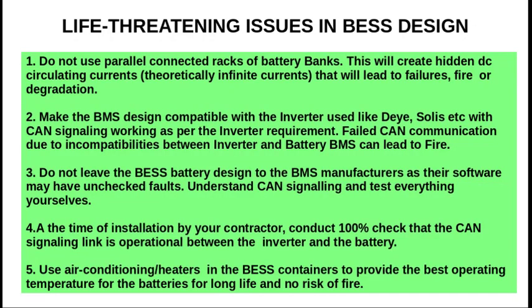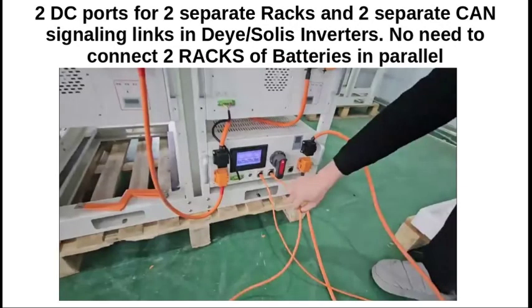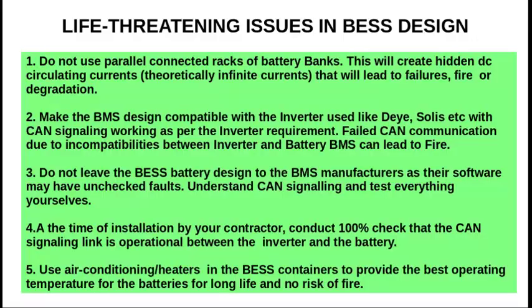Life-threatening issues in BESS design. 1. Do not use parallel connected racks of battery banks. This will create hidden DC circulating currents that will lead to either fire or failures or degradation of the batteries. Point number 2, make the BMS design compatible with the inverter used, like Deye, Solis, etc., with CAN signaling working as per the inverter requirement. Failed CAN communication due to incompatibilities between the inverter and battery BMS can lead to fire.